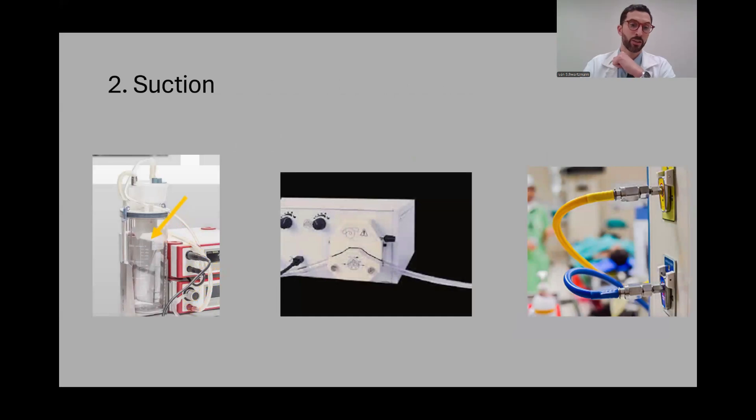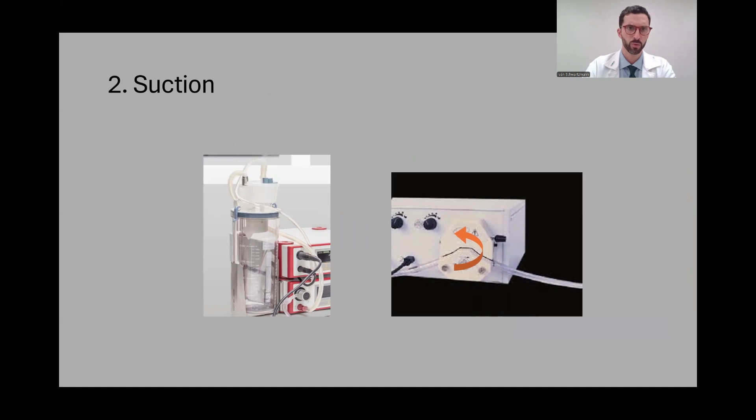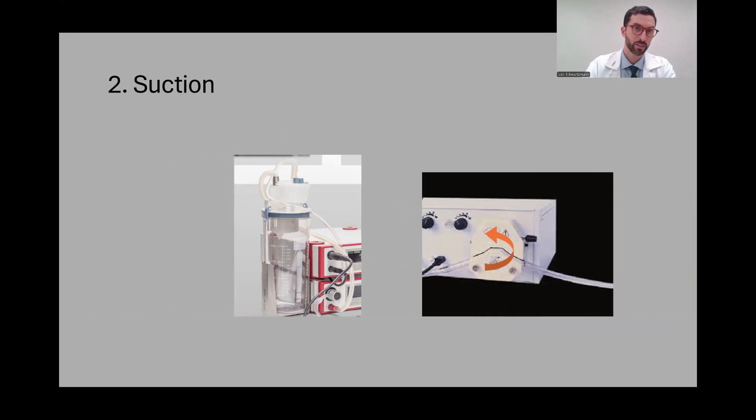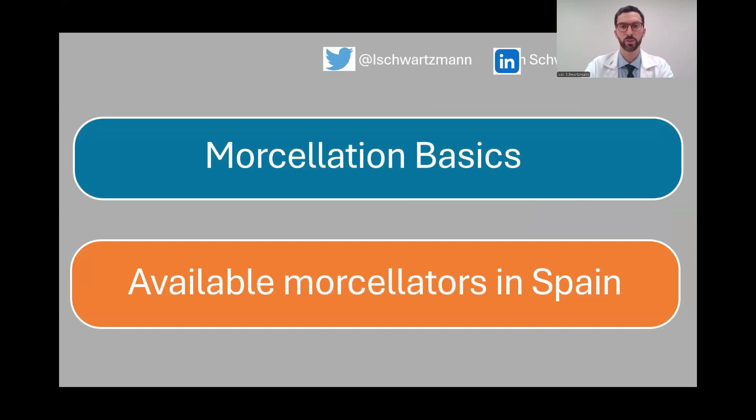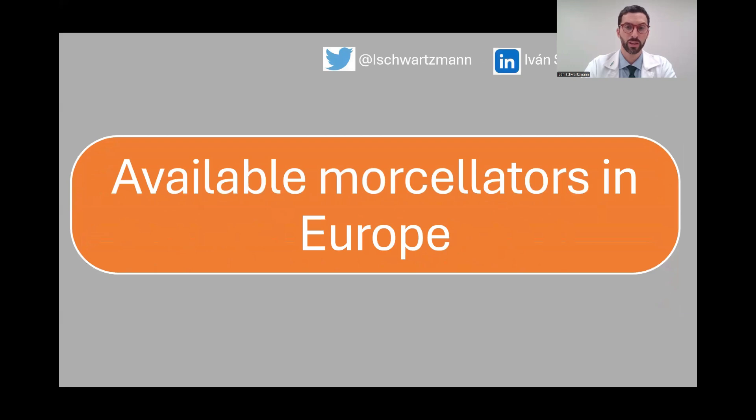The suction mechanism can be one of three mainly: a vacuum generator, a peristaltic pump, or connecting the morcellator to the OR suction. I really don't recommend this last option because it's rarely strong enough to perform good morcellation. So basically two: vacuum pump or peristaltic pump.